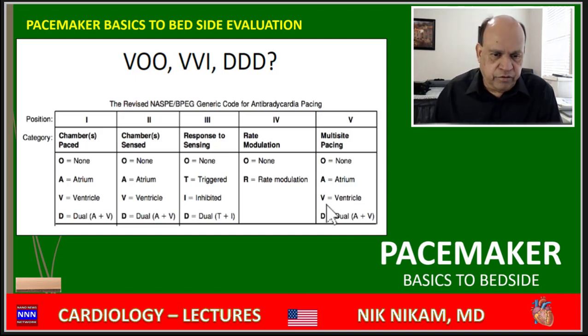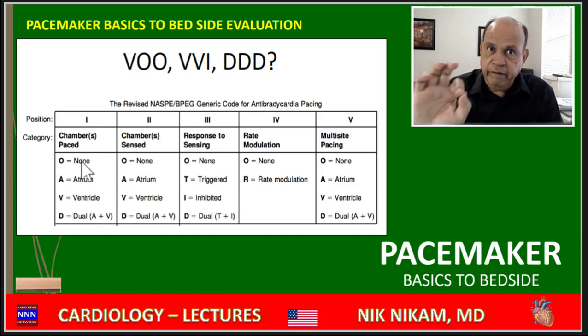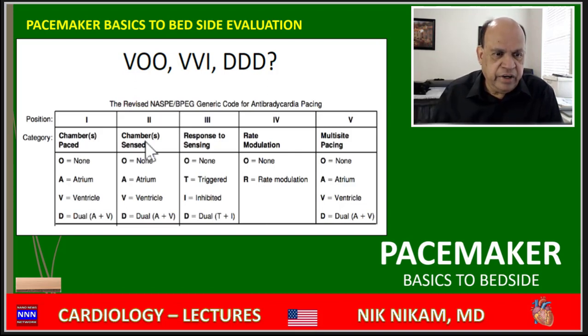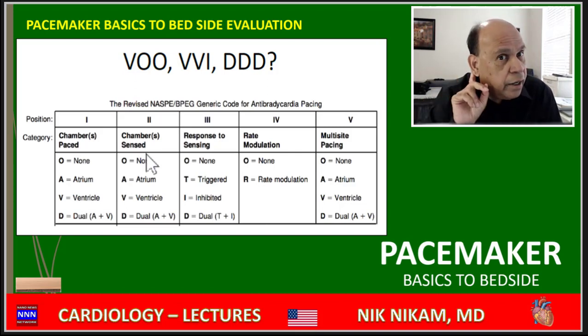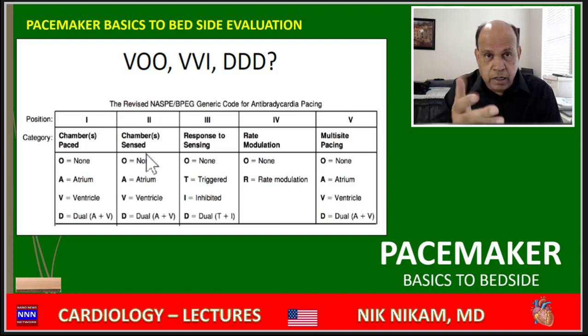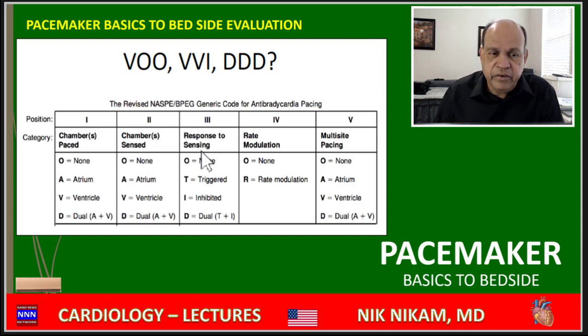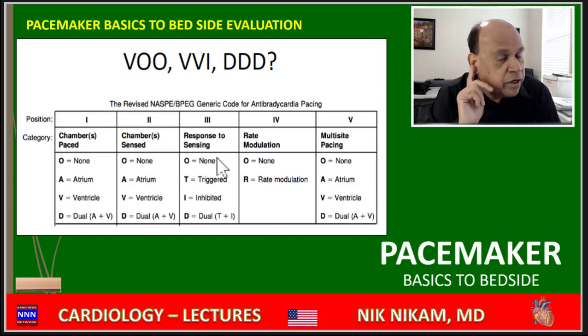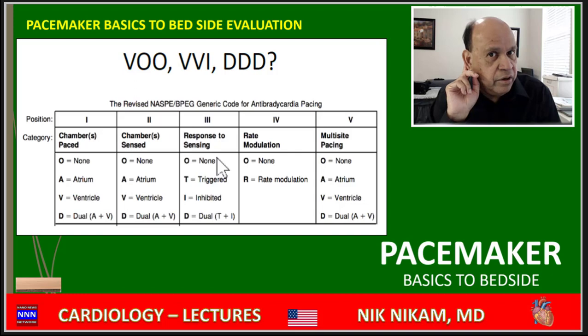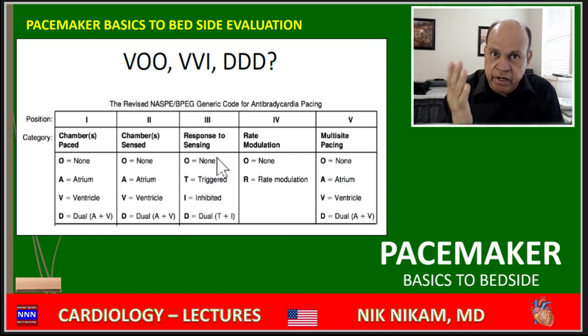Let's look at some of these functions, which are designated by letters. The first letter represents the chamber being paced or activated. The second is sensing - the pacemaker hears the heartbeat, and once it senses a beat, it knows it's good and doesn't need to fire; if there's no beat, it fires. So it knows when it needs to be inhibited and when it needs to trigger activity.